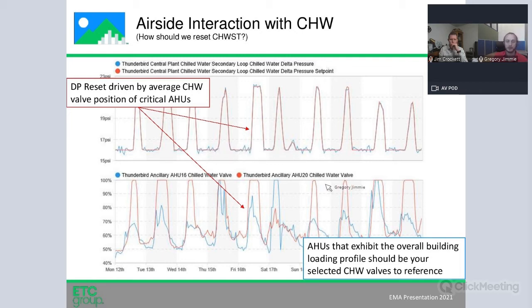One thing to note is that the air handlers are not necessarily your most important or end of the line, but those are maybe good indicators. But the real takeaway is that you want air handlers that move up and down, that ebb and exhibit that profile that your building does as a whole. Those are realistically the ones that you want to incorporate into your differential pressure and chilled water resets, because they're going to be acting as a proxy for the overall building needs.